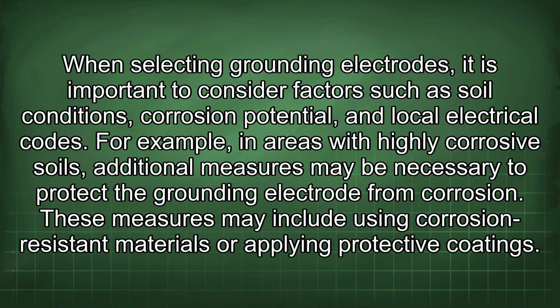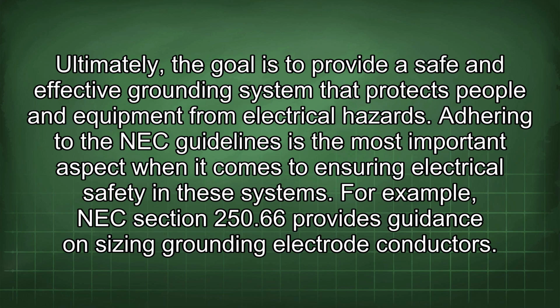When selecting grounding electrodes, it is important to consider factors such as soil conditions, corrosion potential, and local electrical codes. For example, in areas with highly corrosive soils, additional measures may be necessary to protect the grounding electrode from corrosion. These measures may include using corrosion-resistant materials or applying protective coatings. Ultimately, the goal is to provide a safe and effective grounding system that protects people and equipment from electrical hazards. Adhering to the NEC guidelines is the most important aspect when it comes to ensuring electrical safety in these systems.